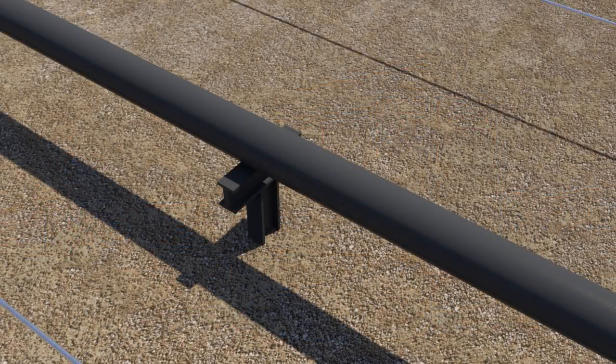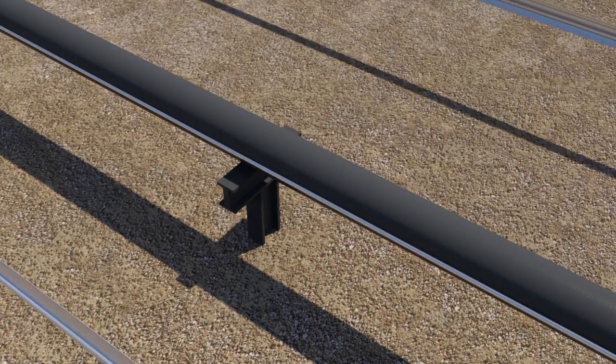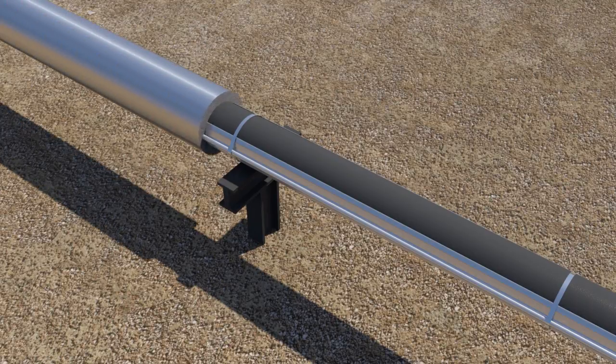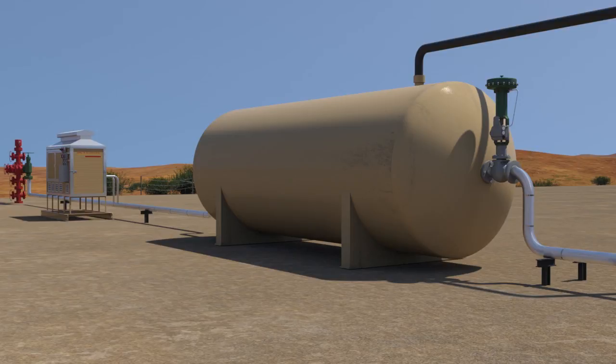Installation begins with placement of heat trace tubing. QMax aluminum extrusion is then installed along with a heat transfer compound and banded. This specialized extrusion increases the heated surface area. A single tracer with the addition of QMax can achieve the same results as 2 to 3 tube tracers. Insulation is then added to prevent heat loss. Insulation should be added where required to minimize heat loss and maximize heat transfer.